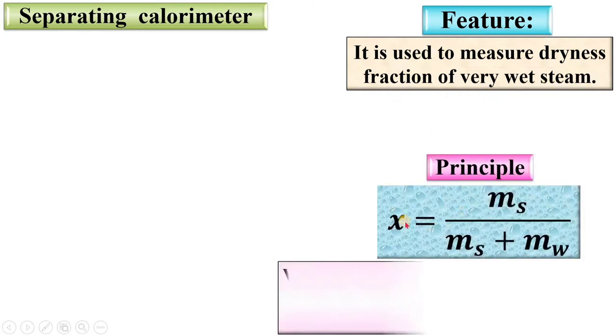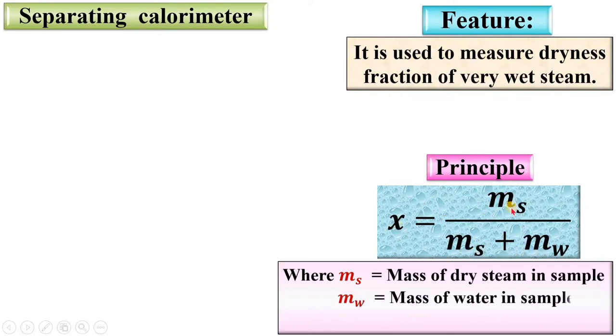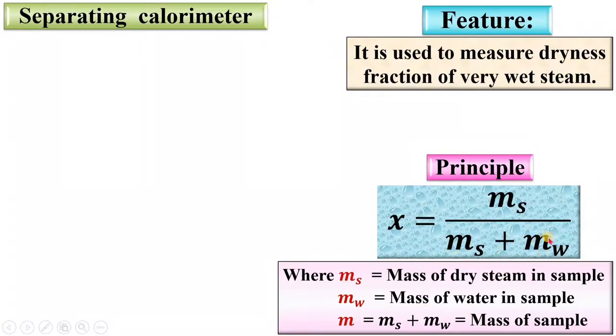Now let's see the principle. The dryness fraction of steam x is equal to ms upon ms plus mw, where ms is the mass of dry steam in the sample, mw is the mass of water in the sample, and ms plus mw is the total mass of the sample, denoted by small m. If you are able to find the mass of the steam and mass of the water in the sample of steam, then definitely you can find the dryness fraction of the steam using this formula.